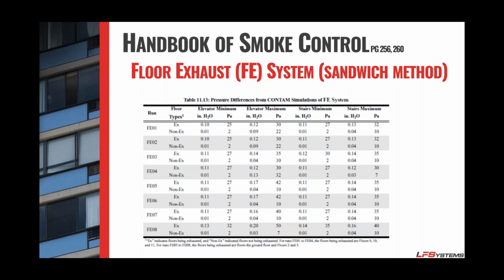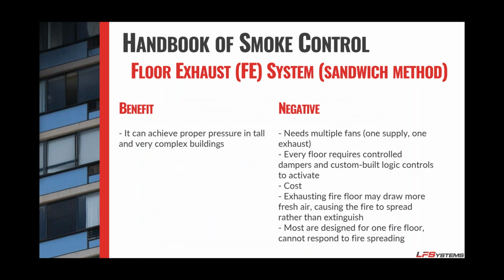However, there's a couple of concerns. While it can achieve the proper pressure, you do need multiple fans. If one of those fans doesn't operate, the entire system fails. Every floor now requires a control damper, as well as a custom-built logic control system to activate those dampers. So when the fire alarm goes off, that controller now has to know where the alarm is activated, open the proper damper, and then activate the proper fan, right? So obviously there's a lot of cost, a lot of custom work involved in that.